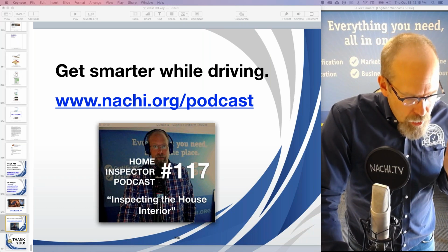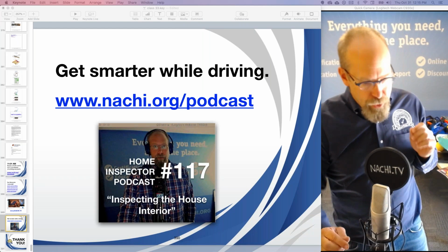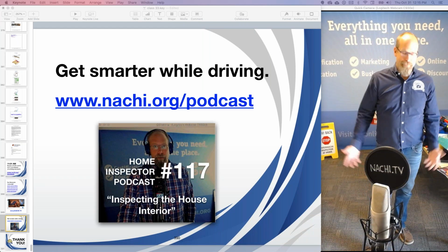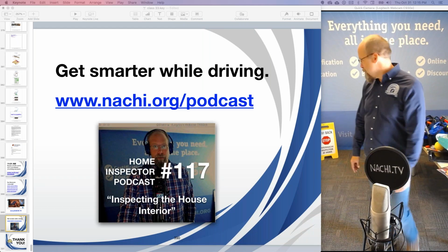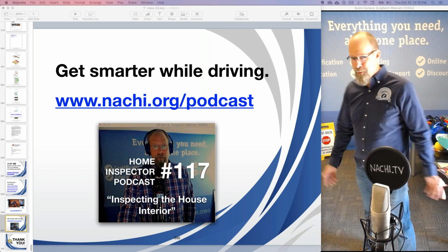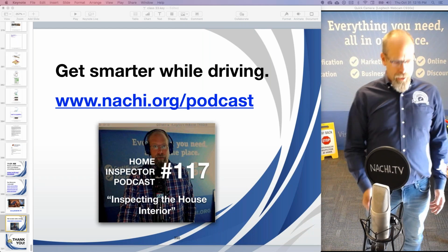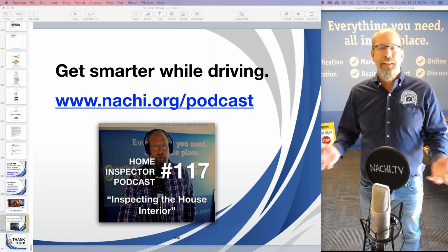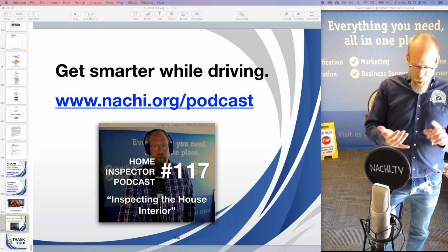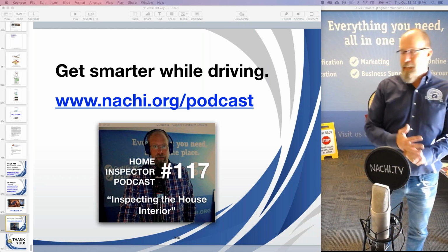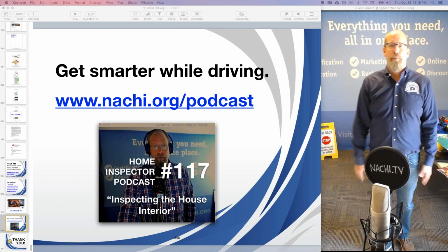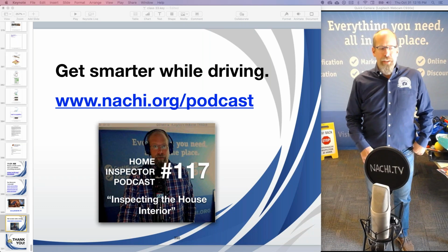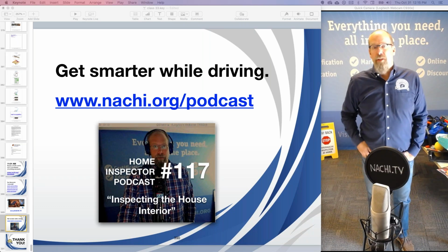Would you call a retro two-prong with no ground a defect? Yes. Because modern day receptacles have a ground, right? So if you're expecting to buy a home that's built to standard, you want AFCIs protecting everything, just like a modern home is. You don't want an agent to try to convince you that it's grandfathered.